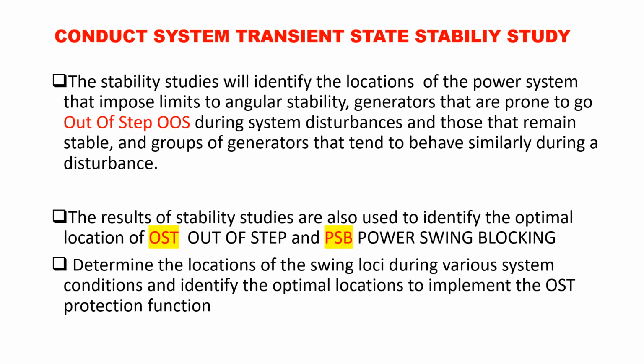So then there is another application we can do, that is the OST, out of step tripping. Out of step tripping means that we deliberately trip the lines or the transformers at certain locations, so that some of the generators which are now going out of synchronism may be isolated from each other, so that they can come back to a normal rotor angle, and they keep on supplying the load.